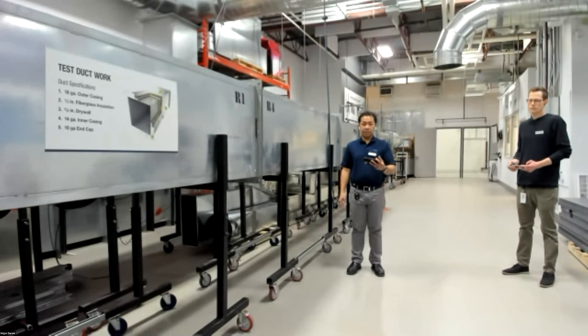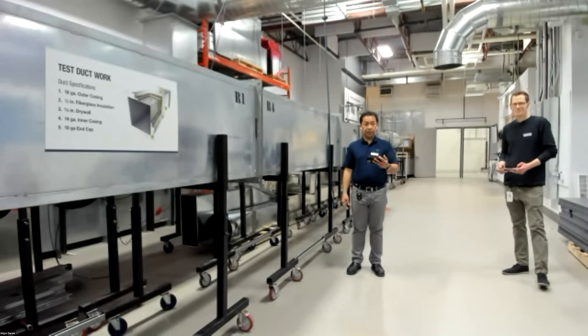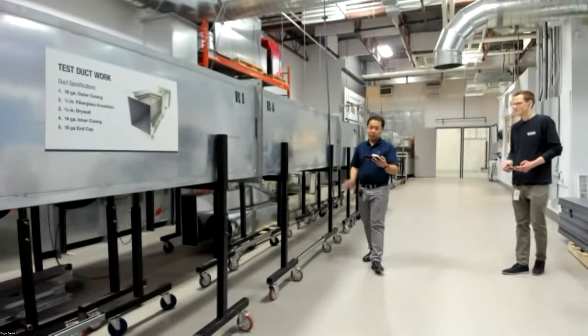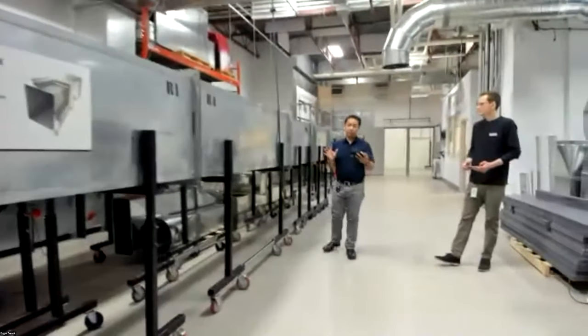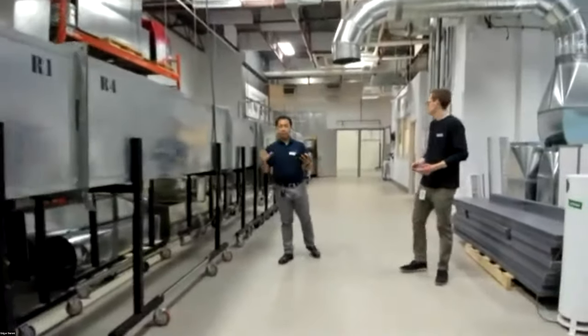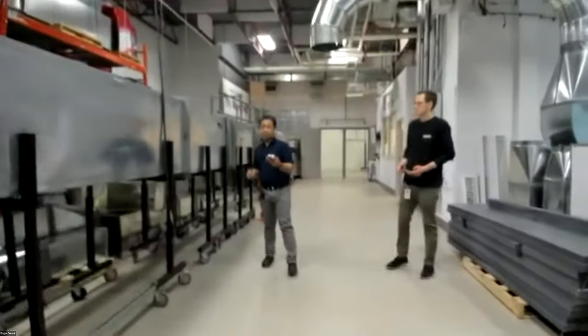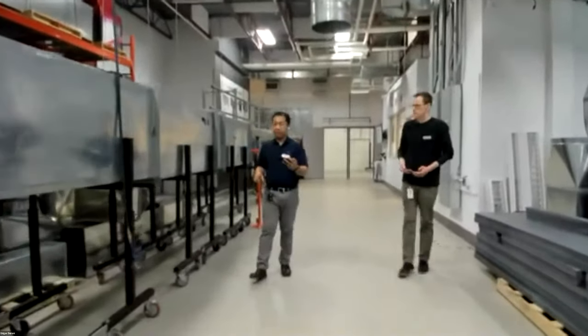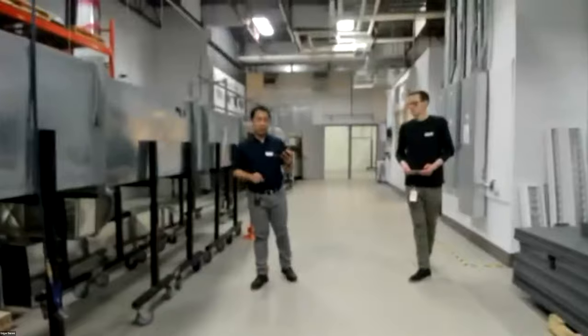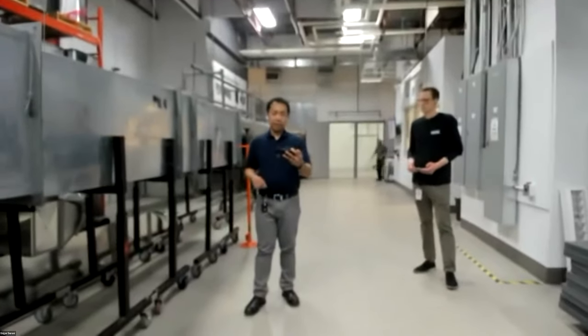We've gone to great extents, and each piece of that ductwork weighs like several thousand pounds. So maybe you're getting some workout moving them in and out, but it's what you need to get really accurate results. Correct. And as you go longer and longer silencer, it's more and more effective. So we need this ductwork to be insulated so that there's no flanking noise coming in and out of the inlet and discharge sound silencer under test.